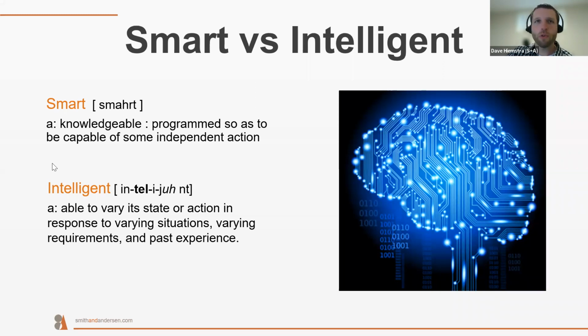Let's use a storage closet as an example. We put an occupancy sensor in there, and it gets left at a 20-minute time delay. Someone walks in and walks out in 2 minutes—we're using a lot of energy we don't need, because those other 18 minutes aren't used. An intelligent system would then have a time delay that adjusts over time based on that usage. After a little while, the sensor figures out that most people are only spending 2 to 4 minutes in there, so it sets a time delay of 4 minutes and gets that energy savings.